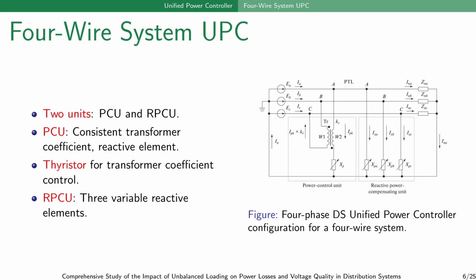While in four-wire system, UPC four-wire consists of two units: the power control unit and reactive control unit. The power control unit uses consistent transformer coefficient and reactive element controlled by thyristor to control the power between the three phases, while the reactive control unit, on the other hand, uses the same technology but to compensate the reactive power in the three phase.